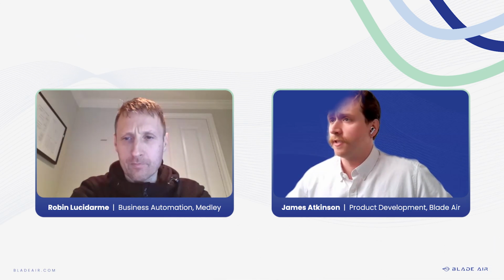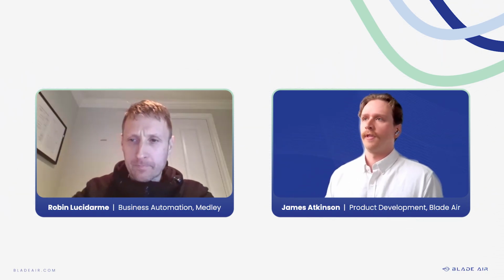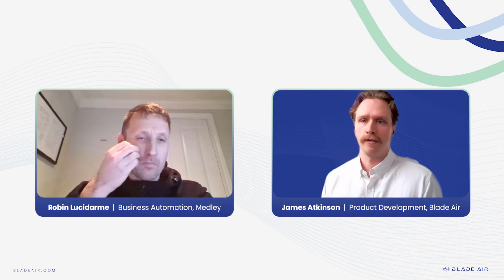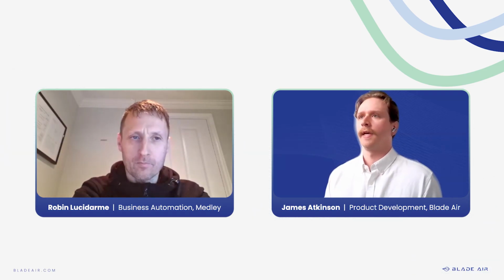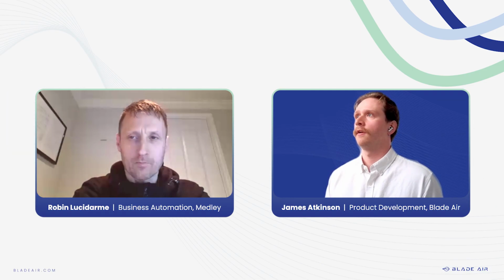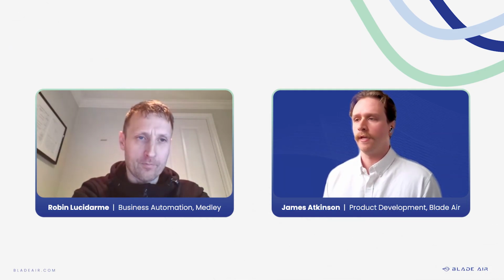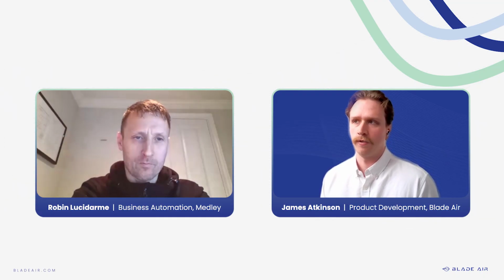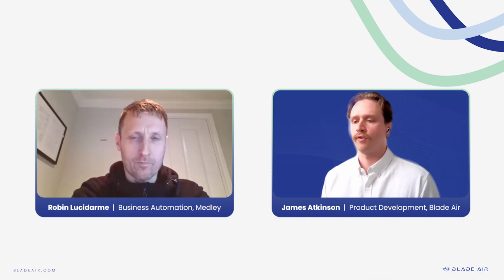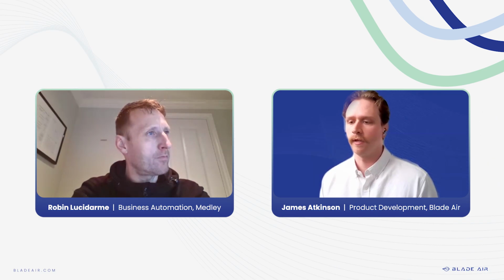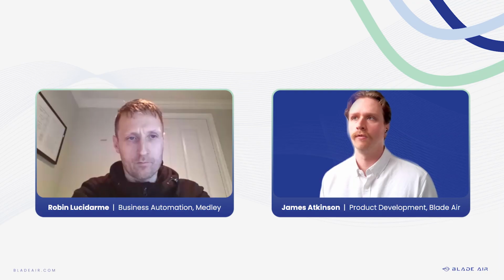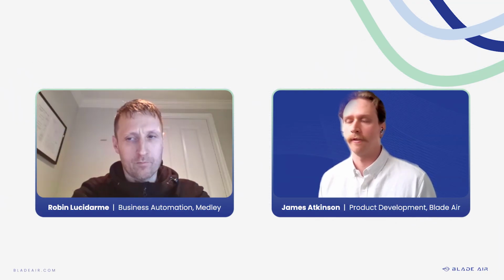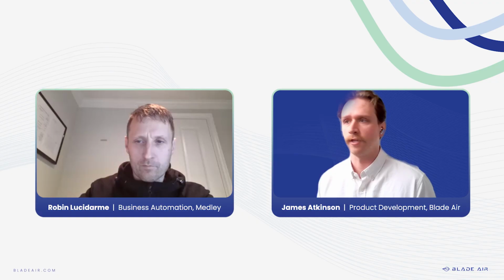Any questions about the IAQP versus Standard 62? I know I went through it quite fast just for timing. I think the main thing I wanted to stress is that Standard 62 is a prescriptive standard that really just guarantees ventilation. It doesn't guarantee really safe indoor air. Whereas the IAQP is a more practical, data-driven procedure: after you've designed your building with ASHRAE 62 for, let's say, code compliance, you can then reduce your airflow by tracking the real pollutant concentrations in your building. And then you're titrating your fraction of outdoor air to see what you actually need to dilute the pollutants and make sure that there's a healthy space. I think that's really distilling the information.